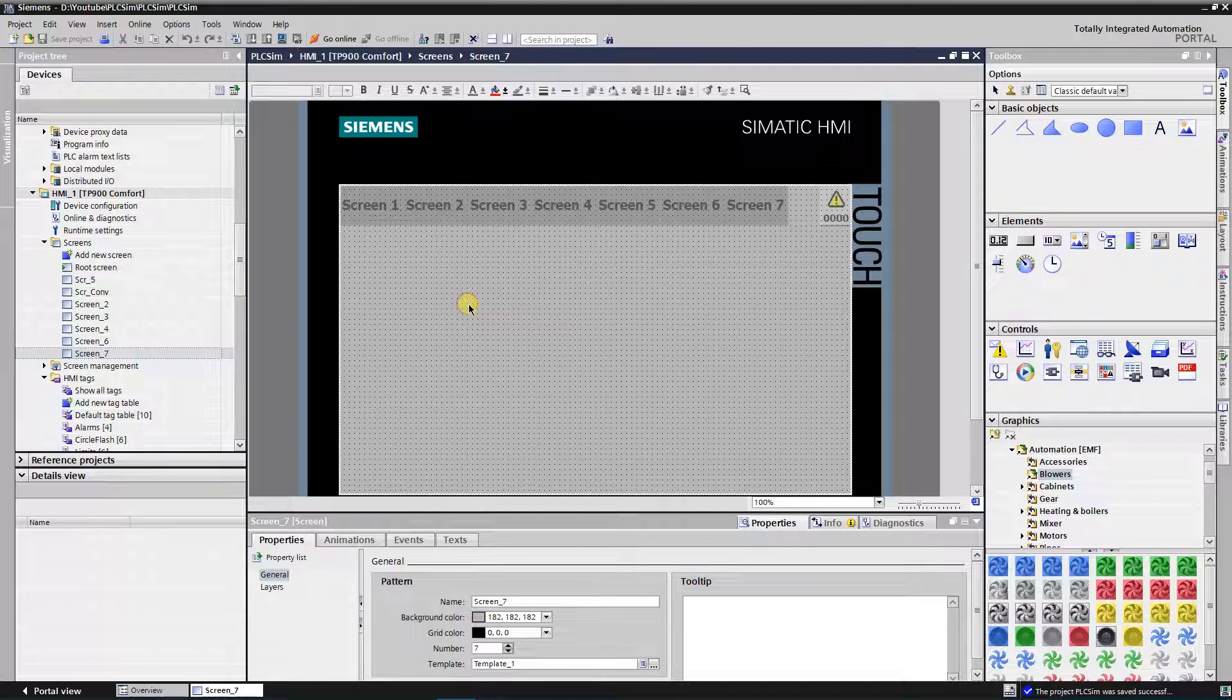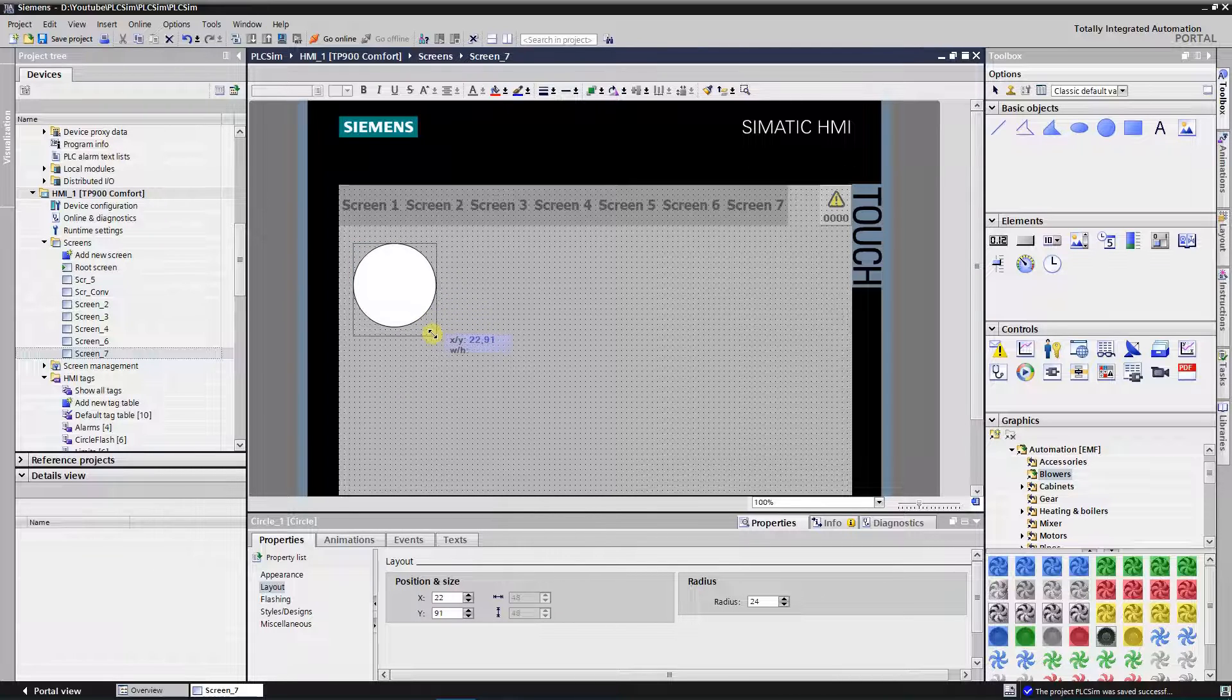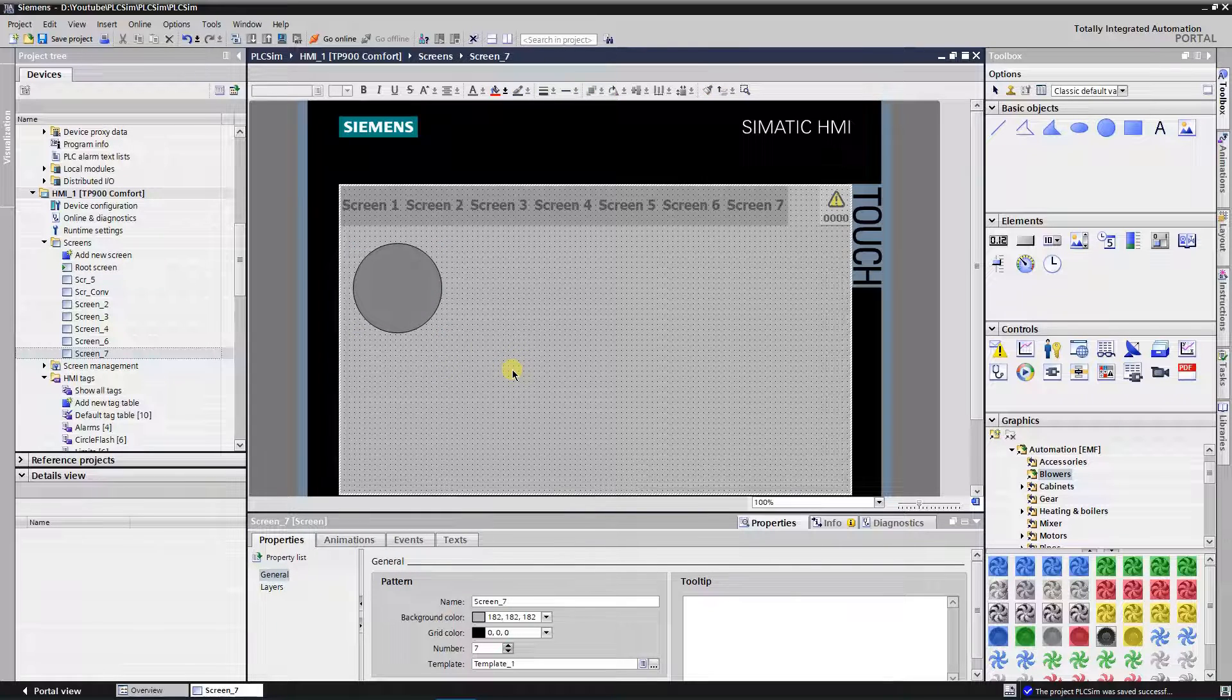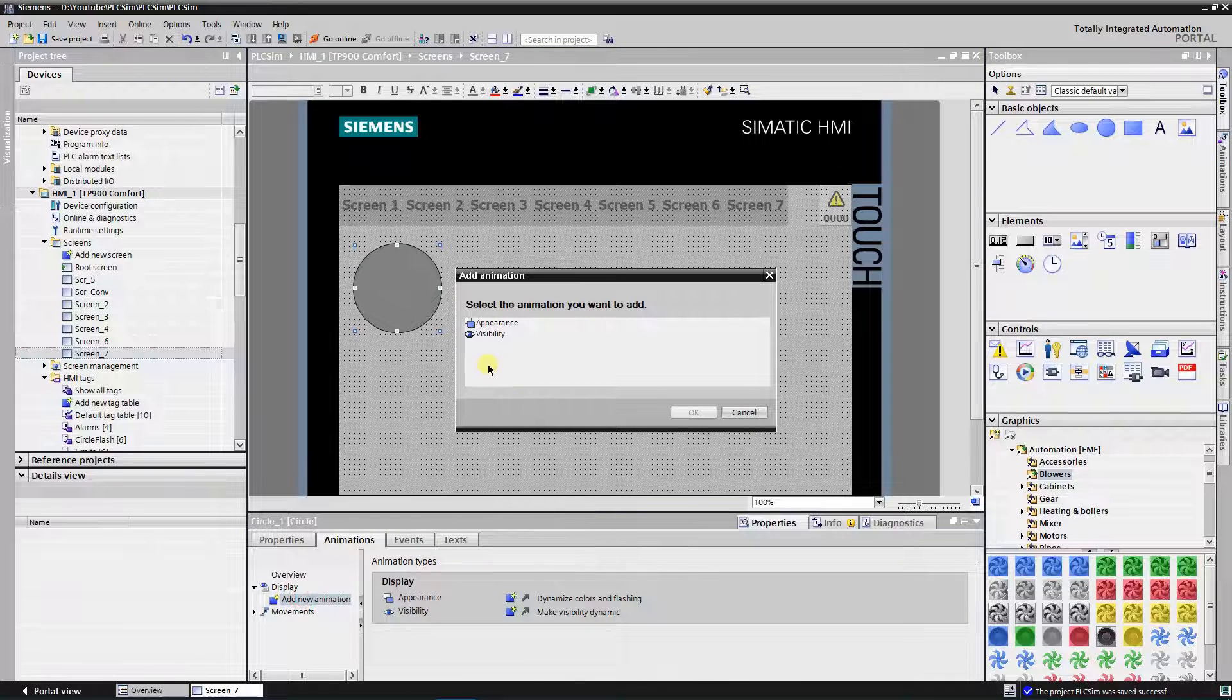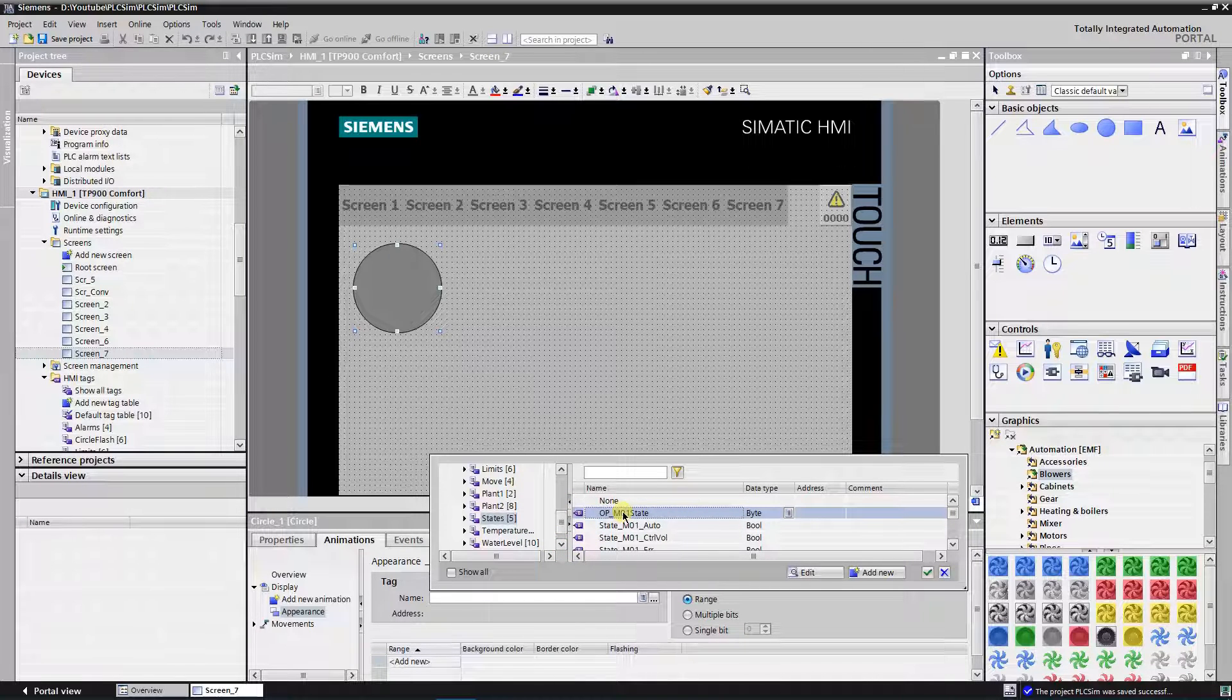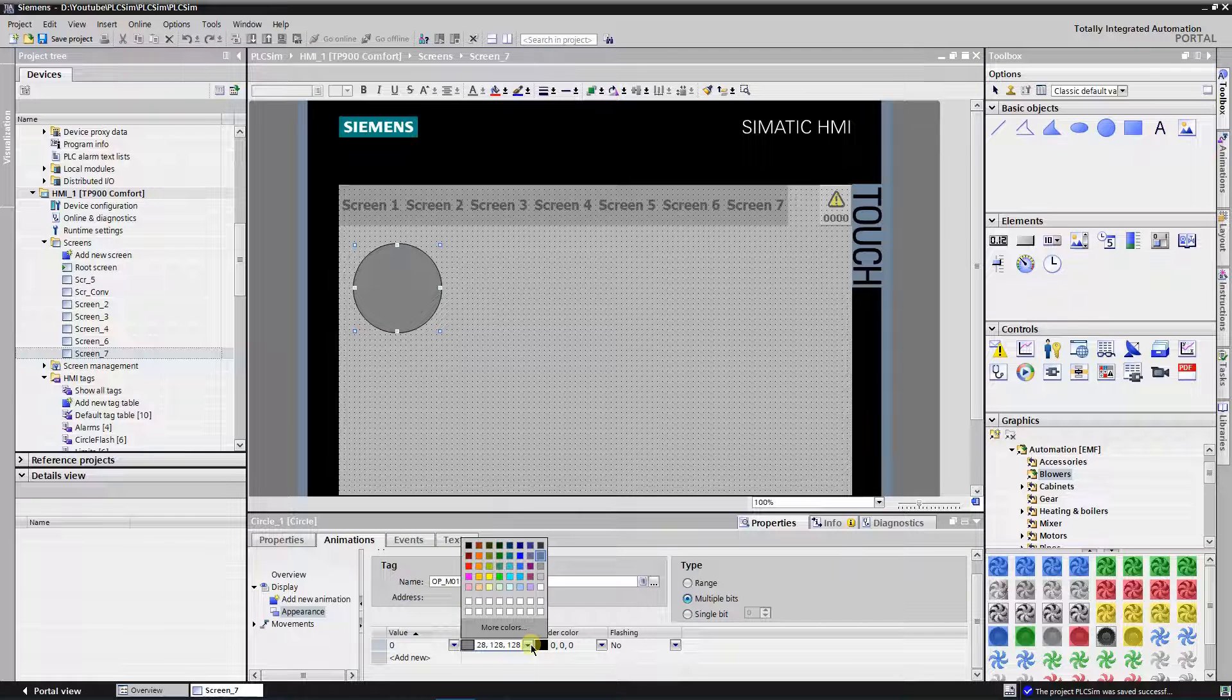Find the circle from the tool box, drag and drop it onto the screen. You can change the background color of it, but it is not needed in the design mode. Switch to the animation tab of the circle and expand display. Double click add new animation and select appearance from the opened dialog. Assign tag where bits with state information are stored. Select multiple bits as type. Bit 0 is not used in my example, so I will select a neutral gray color.